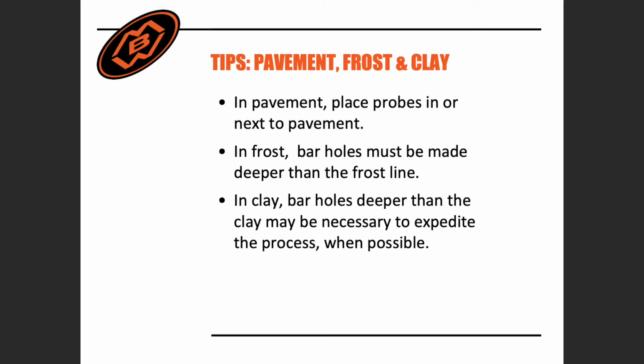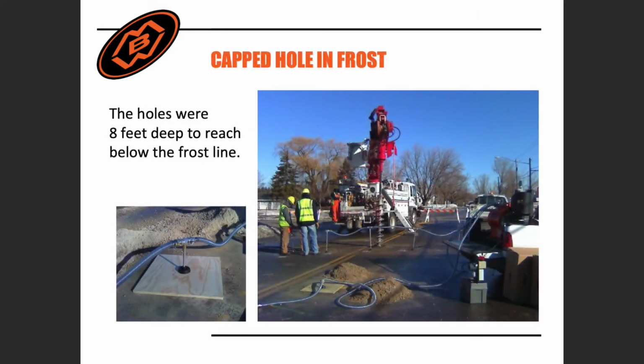In this slide, we were up north and had to get out the telephone pole auger to dig out bar holes below the frost line. The bar holes had to go 6 to 8 feet deep to get below the frost line. Now keep this in mind, this is a rare and extreme occurrence. This was a very cold winter in Wisconsin. Please note that we had to be creative and use plywood to seal off and cover the larger than normal bar holes for the VEU probes.